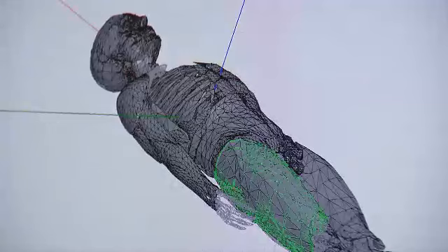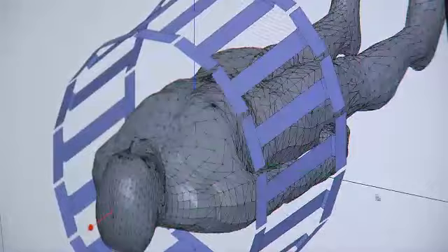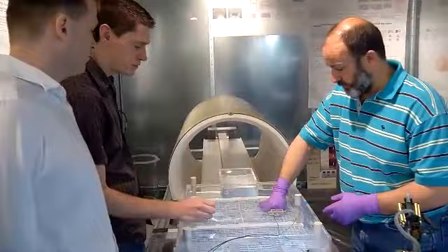We created a human body library spanning approximately the 2nd to the 97th percentile of the human population in terms of size and shape. In addition to that, those bodies were electrically correct from an RF perspective. We don't have confidence in the results unless we validate this by comparison with measurements. And obviously, we could not perform model validation directly in humans. To validate the model, we used a body phantom as a surrogate for a human, trying to represent the human as best we could with this non-human structure.